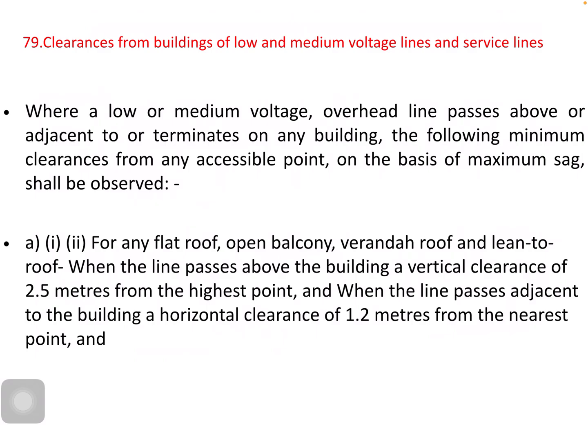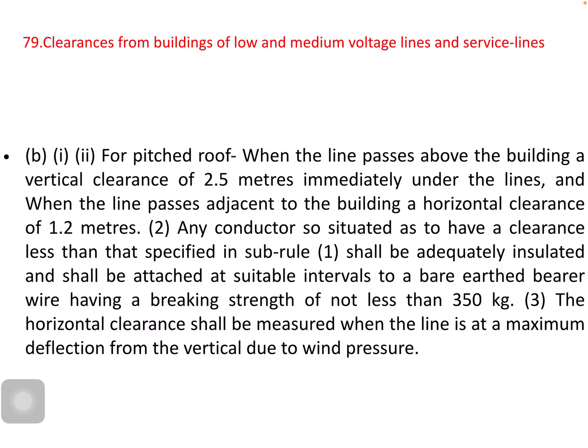Rule 79 talks about the clearance from buildings of low and medium voltage lines and service lines. That is, the minimum height from the rooftop for any flat roof or lean-to roof: the vertical clearance should be around 2.5 meters from the highest point, and horizontally it should be 1.2 meters. If it is a pitched roof, then the vertical clearance should be 2.5 meters and 1.2 meters horizontal. It should be properly insulated, and a wire having a breaking strength of not less than 350 kg should be provided. It should not deviate due to wind pressure.